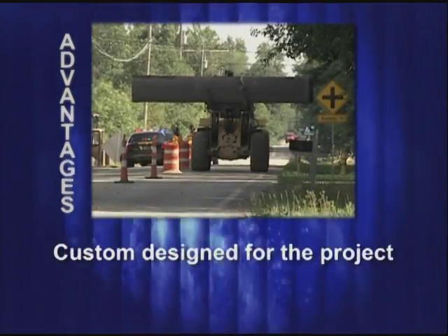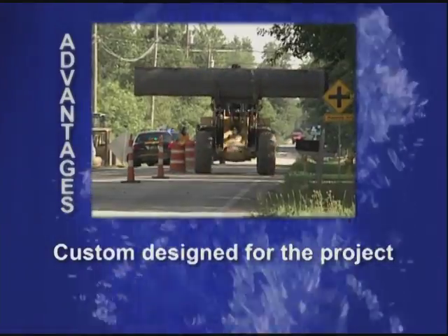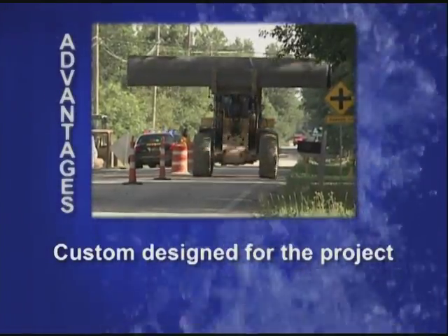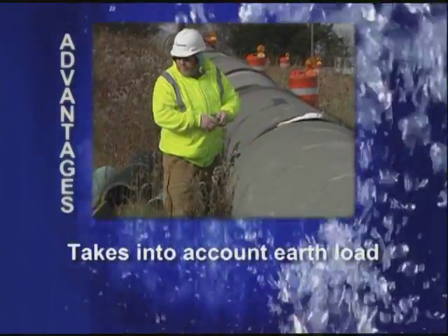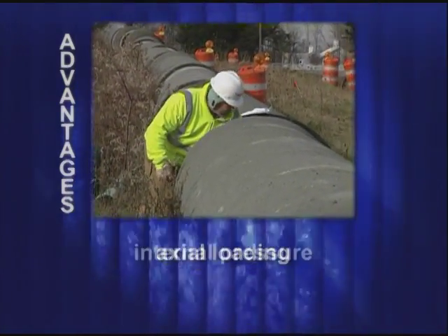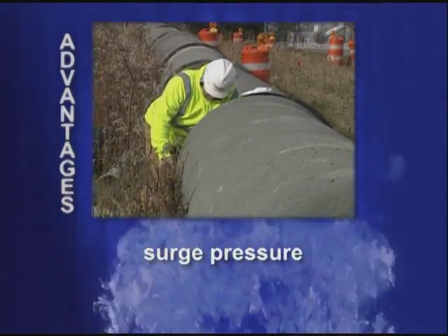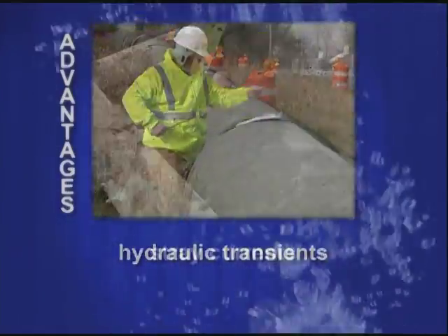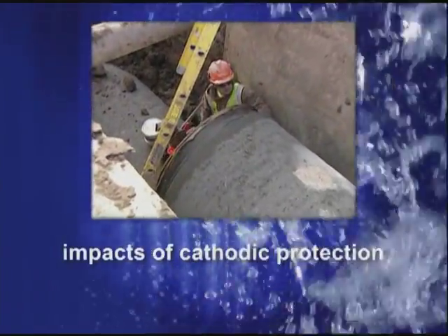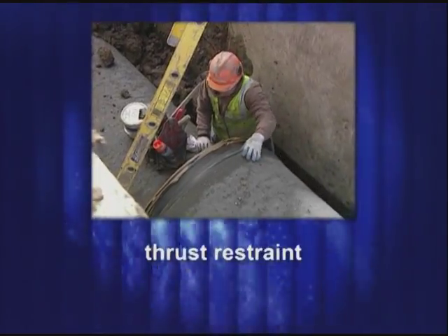Another advantage is that each type of concrete pressure pipe is custom designed for the project. The design procedures take into account earth load, live load, axial loading, internal pressure, surge pressure, hydraulic transients, stray currents, impacts of other cathodic protection systems, and thrust restraint.